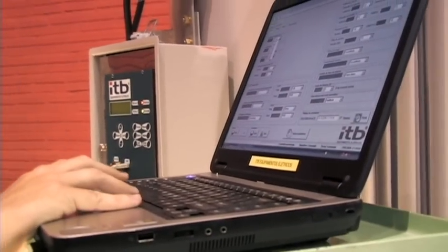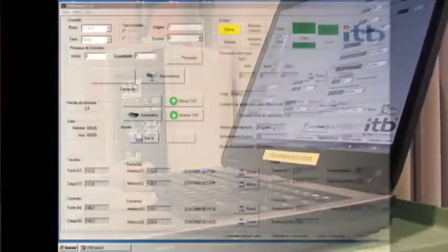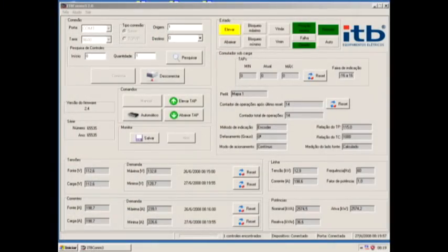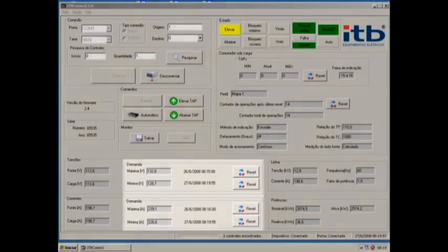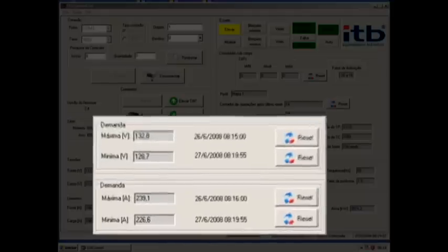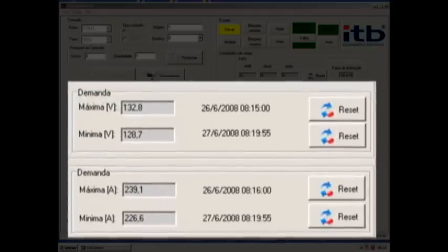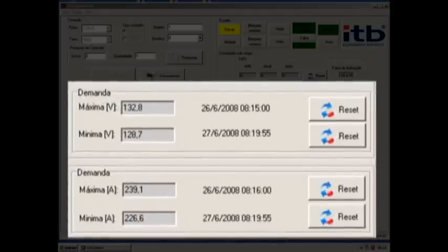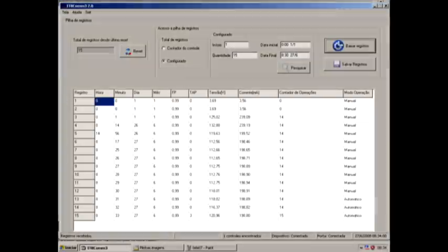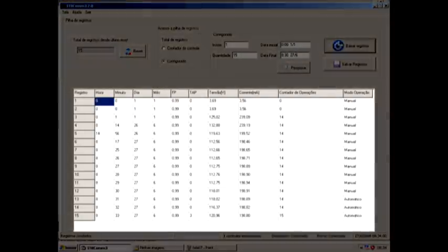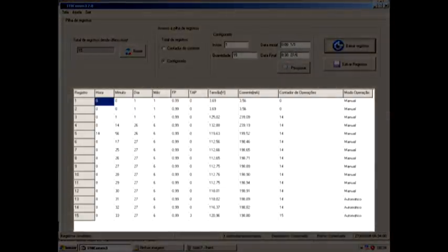The electronic controller can log events, recording, storing and displaying the date and time of the last update of voltage and current minimum and maximum demands. It can also record, store and display the number of registers in a preset time period, adjustable between 1 and 60 minutes.